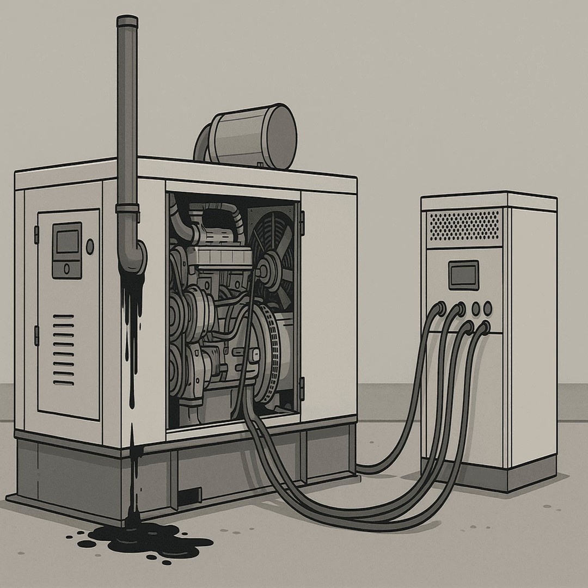The long-term outlook isn't good if it's not addressed. You're looking at decreased engine performance, definitely lower efficiency, meaning you burn more fuel for the same power output, and just generally reduced power capability. It might run rough. Yeah, the engine might misfire, run unevenly, maybe produce continuous black smoke even when it's under a steady load, which is different from the puff of smoke on startup. In really extreme, rare cases, the accumulated fuel in the exhaust could potentially ignite if temperatures suddenly spike, which is obviously very dangerous. Good grief.